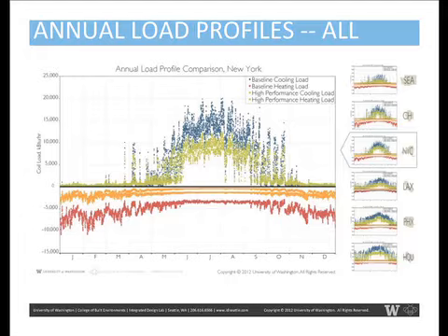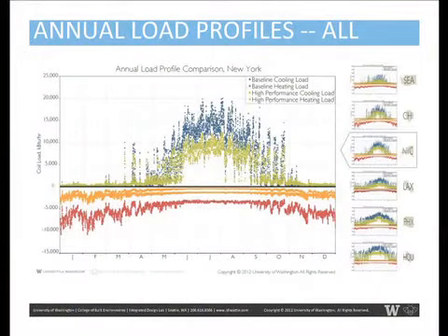And one thing that our mechanical engineer likes to point out, which I think is pretty interesting also, is that this almost looks like a mistake on the high performance heating load. It looks like it's repeated data in the graph. But really what it is, it's the turn down at night. So for example, the ORs and the kitchen and the ED, when they're not in use, they're scheduled to be turned way down. They're still an overhead mixing VAV system, but they turn way down at night, and you can see the implication on the heating energy for that turn down.